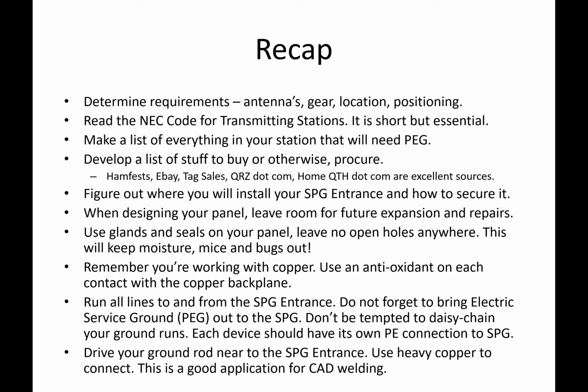KC1DOY: Go ahead, Dad. Yeah, I just wanted to mention, if you have a newer home, you may find they do not use copper pipe anymore - they're using PEX, which is plastic. So you're not going to find a direct route to ground to the pipes. You may also find copper pipes in the house that are connected to PEX somewhere else along the line, especially if you've done remodeling. So always be sure, if you're going to use your water pipes for ground, make sure they really do go all the way to ground and there's not something in between that breaks that connection, because it's quite possible you might find that if you've done any changes.